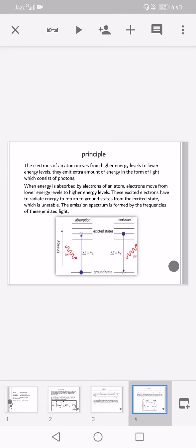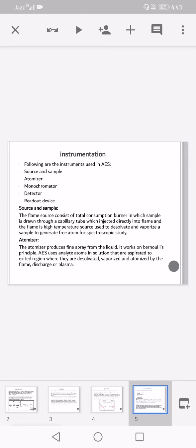Instrumentation: the following instruments are used in atomic emission spectroscopy: source and sample atomizer, monochromator, detector, and readout device. The flame source consists of a total consumption burner in which the sample is drawn through a capillary tube and injected directly into the flame. The flame is a high temperature source used to desolvate, vaporize, and generate free atoms from the sample for spectroscopic study.